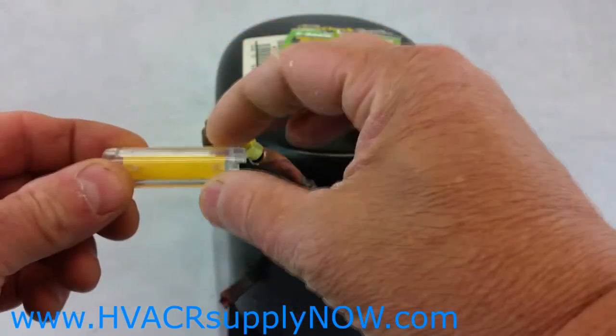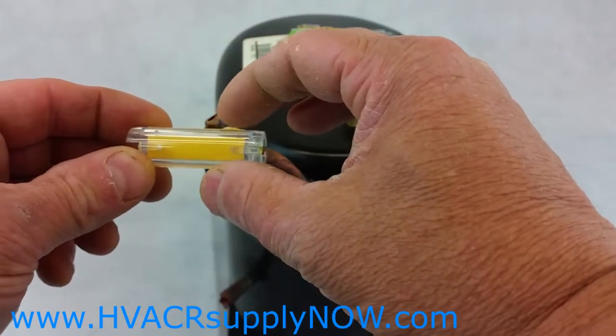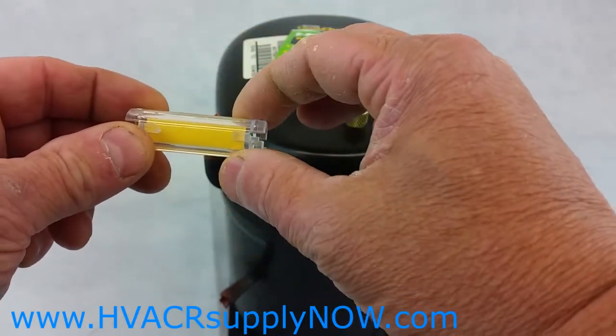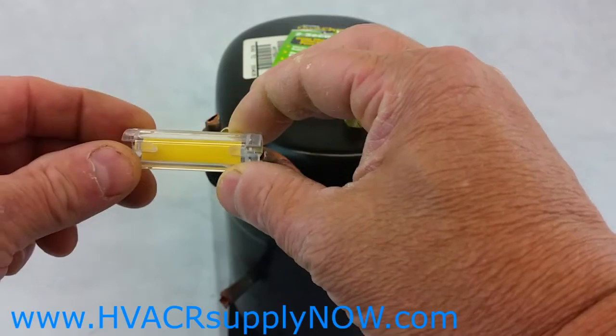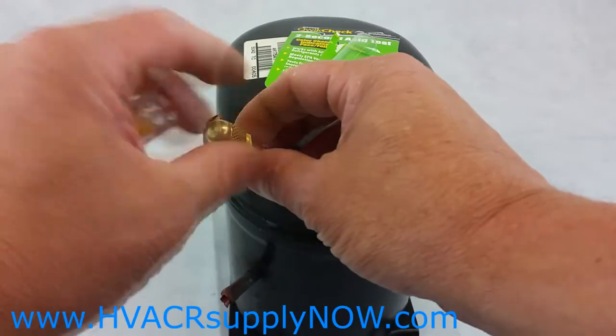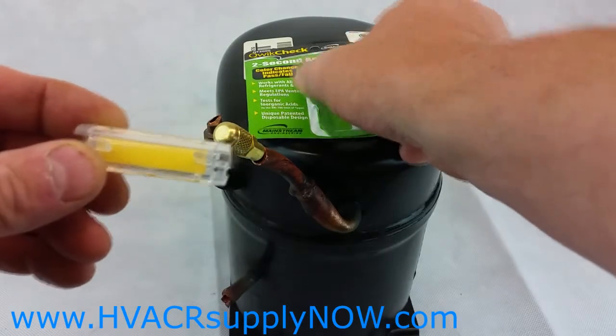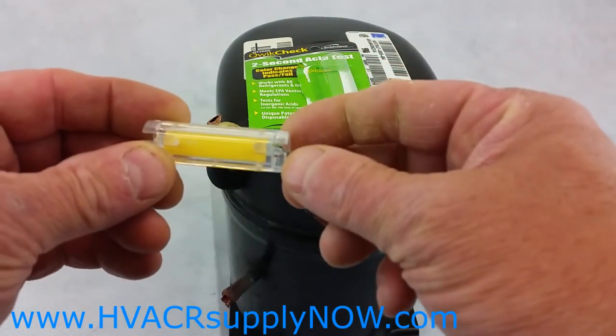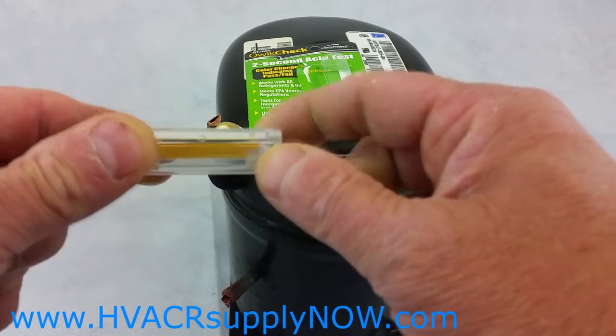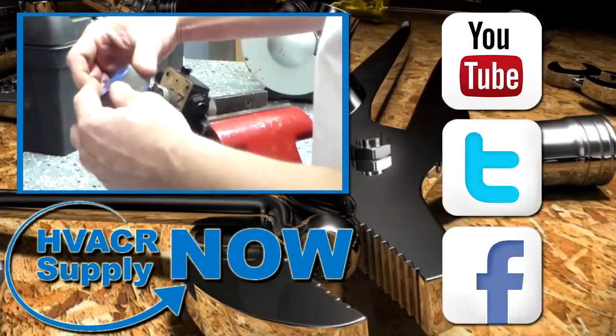Check the paper inside the QT 2000. If there is a change in color, then you have the presence of acid in the system. If the paper does not change color, there's no acid in the system. Tighten it up and make any repairs if necessary. Again, it's the Qwik Check QT 2000 two-second acid test kit, available at HVACR Supply Now. Thank you.